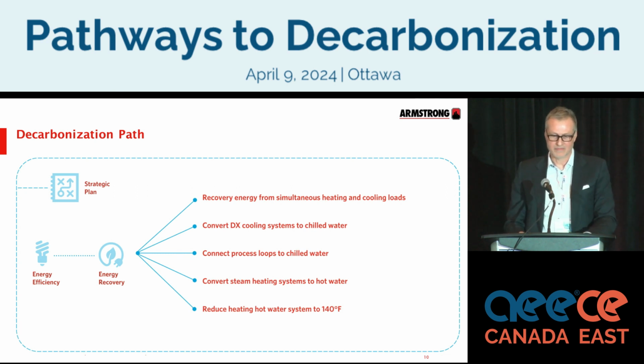And when Matt mentioned the Noventa project in downtown Toronto, Western Hospital, one of the key things that they did there is that the whole healthcare facility actually moved to low temp hot water. They're running at 115 degrees. The capital investment on that was $15 million on replacement of fan coils in the ventilation system. Why? You need the increase in surface area.